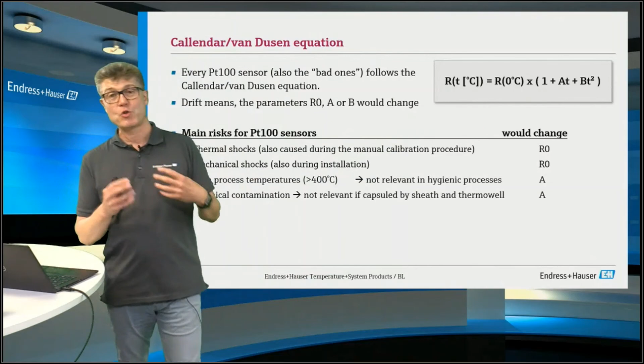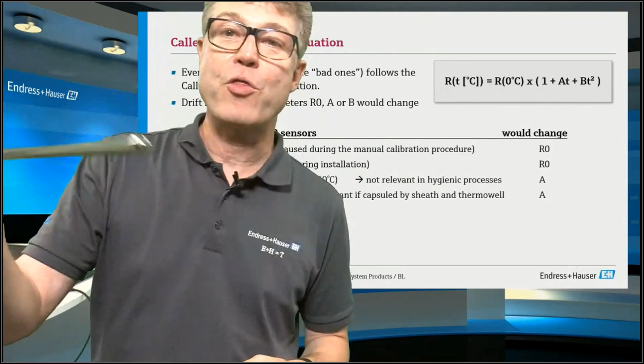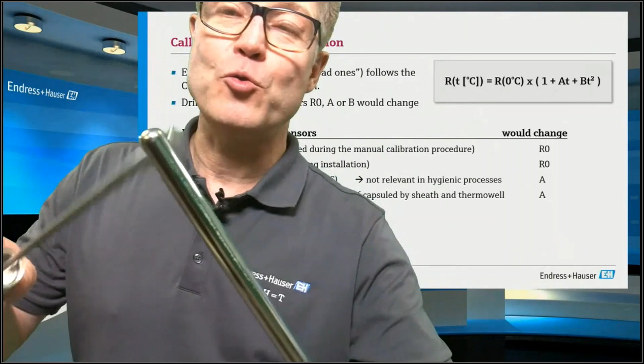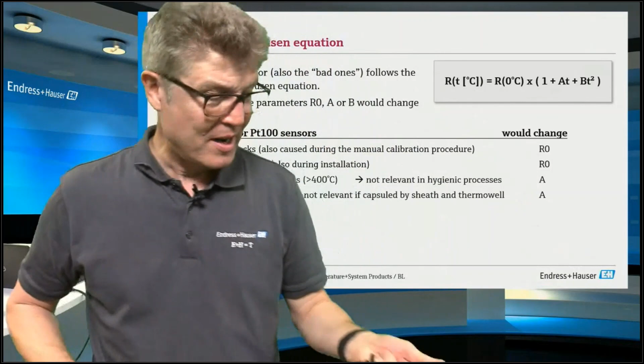And the question is how? How should this be possible? If you imagine, sorry, I was out of the picture, this is a TrustSens with a thermowell. You have a thermowell. So if you want to destroy the PT100 or the Curie material, you have to penetrate a thermowell, a stainless steel measuring insert, crawl into the sensor and exchange the platinum by something else during normal operation, while the signal is not changed. How probable is this? I have no idea. I cannot imagine. So it cannot happen. And also the last one, factor B, might change at temperatures above 200 degrees, outside of the scope.